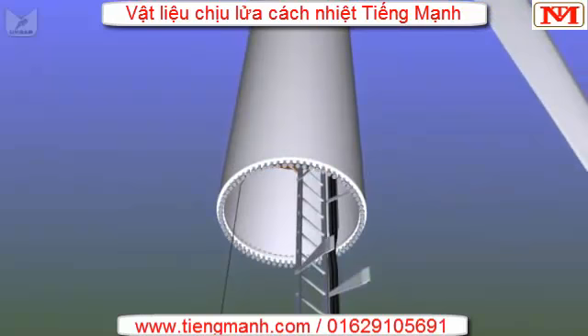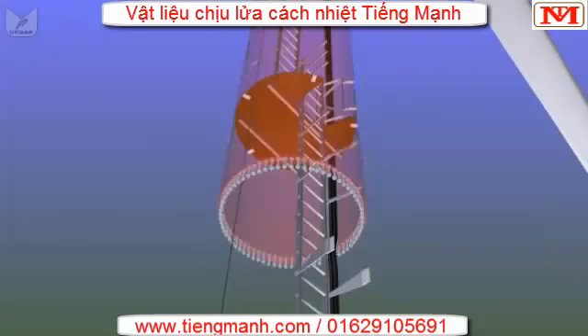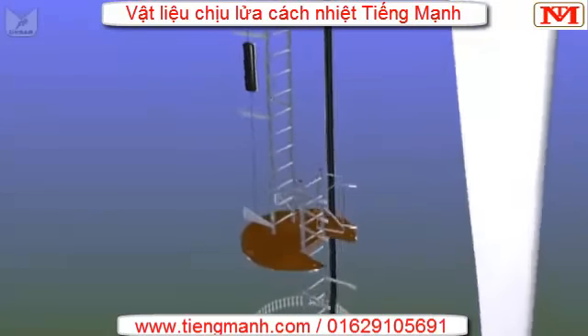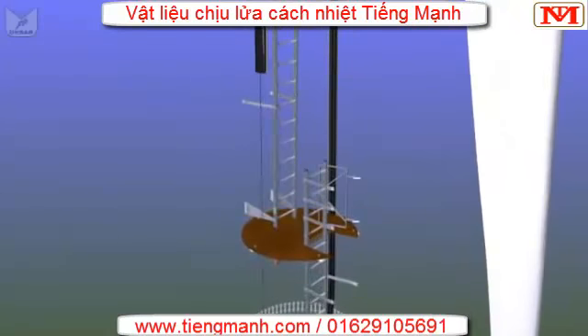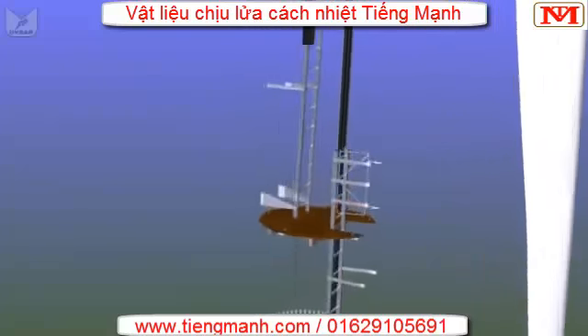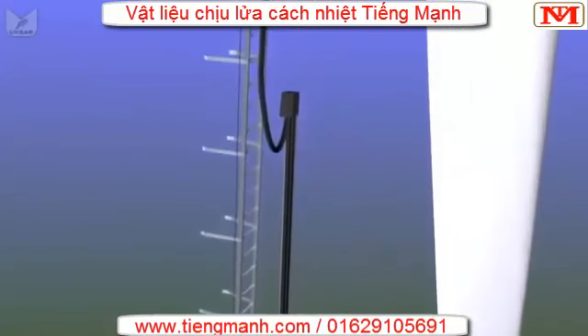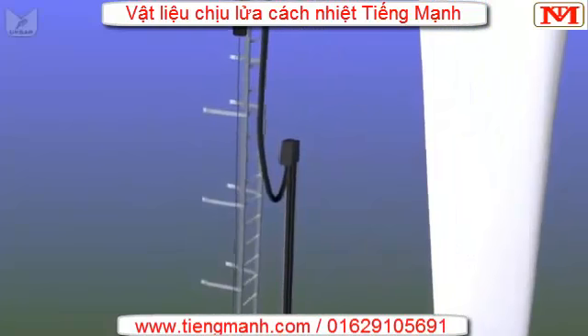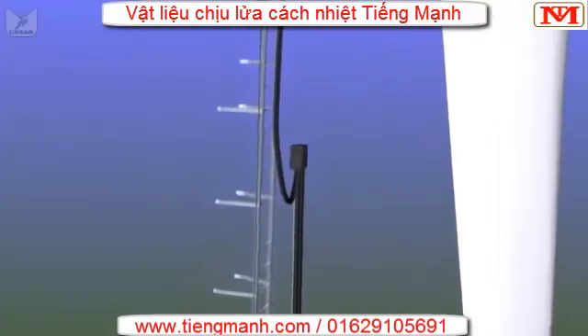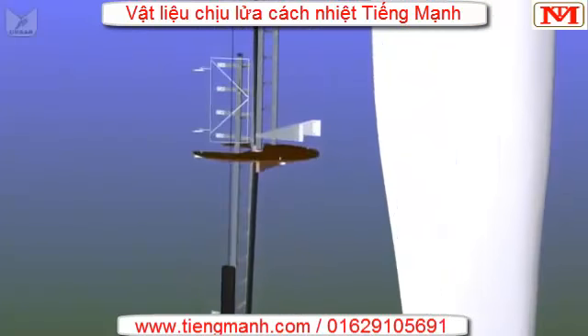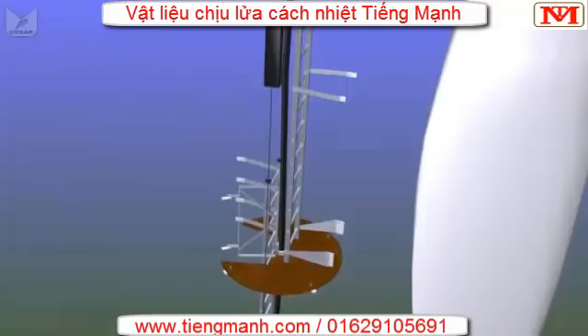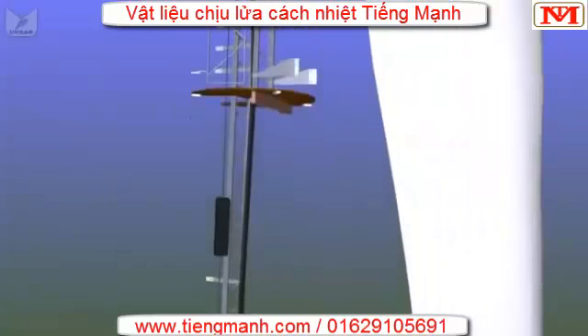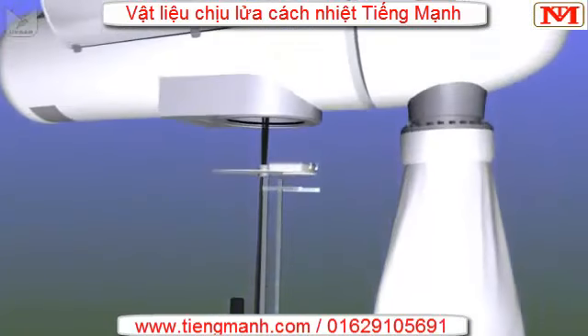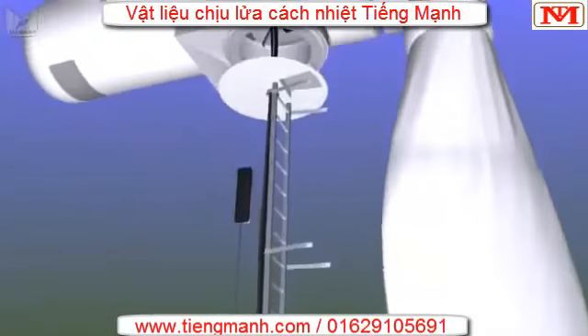But as we move higher and higher through the platforms, they're getting slowly narrower and narrower, so the ladders are getting a little bit closer together. But eventually the main cables stop being attached to the wall and they hang freely in the center of the tower, so they can twist as the nacelle rotates to face the wind. If they twist too many times, the nacelle will spin itself around to remove the twists. As we move up, now the cable goes through a hole in the center of each platform, and at the top of the tower we have a steel platform with a sealed trapdoor, which we call the yaw platform.